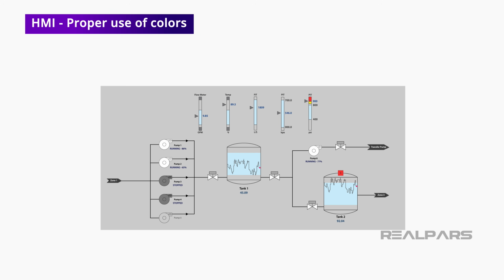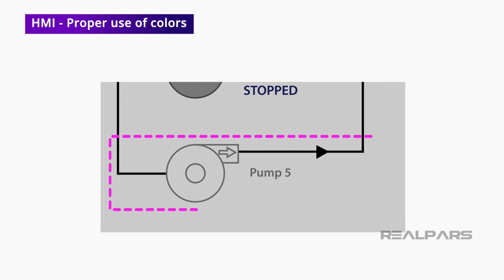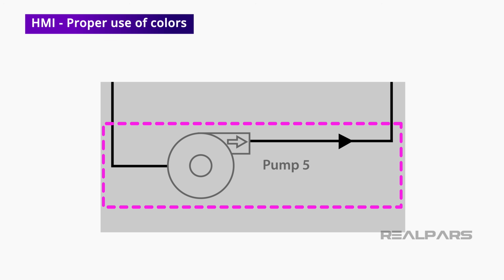When you are working on your project and creating conditions for item visibility, it should be designed so that users can view all commands and configurations of an object. If you are not granting a user group access to modify the configuration of an object, then that object should be grayed out, with the fill of the object matching the screen background, and all lines and text should be light enough to just contrast the fill. An object should not be made invisible because doing so would create confusion if a user or user group is later granted access and sees a new object on their HMI.